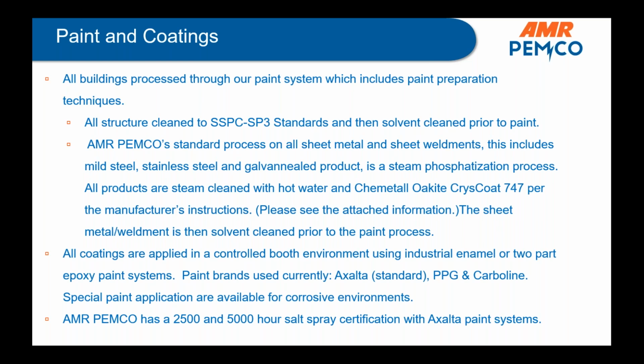All of our paints are either an industrial enamel or a 2-part epoxy. Most of the time we're going to recommend a 2-part epoxy system, which generally has a 20 to 25-year life. We primarily use Axalta as a standard paint, the old DuPont, but we have other paints for special applications, like zinc primers for corrosive environments. We do a lot in the gas space, so we have to be able to paint those corrosive environments well, and in the Southeast with salt or coastal environments, we can handle those too.